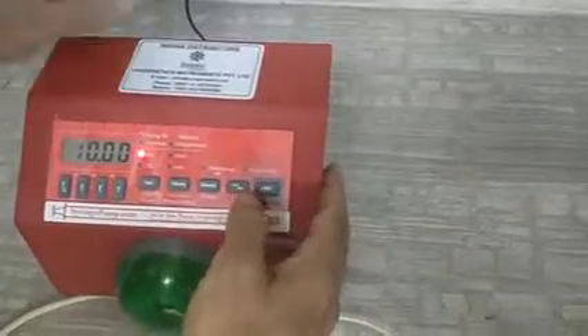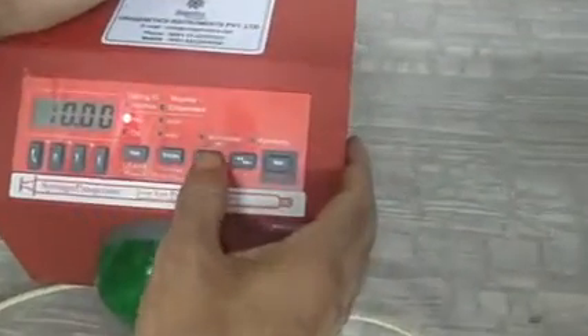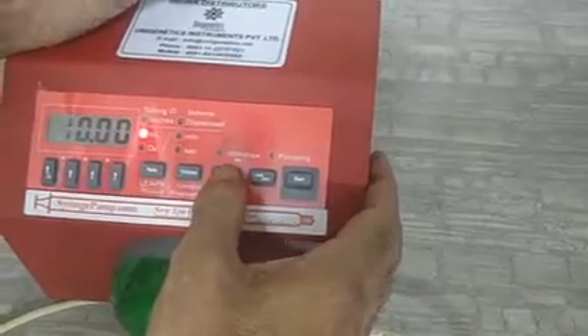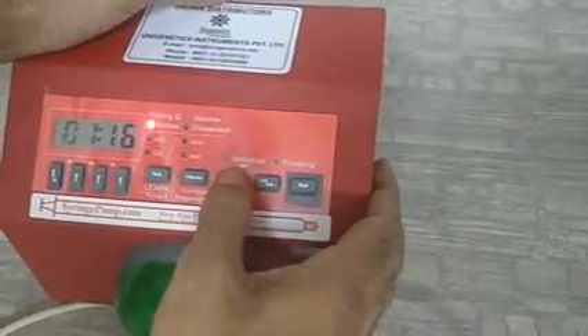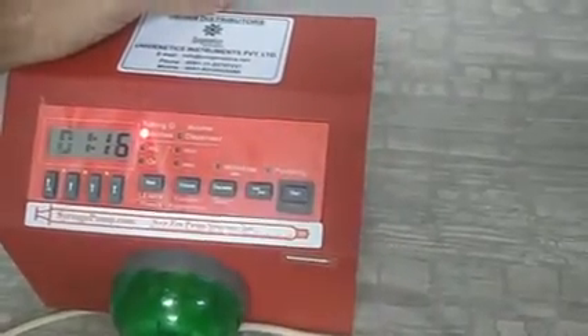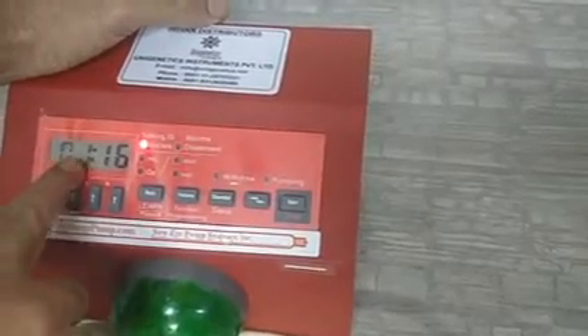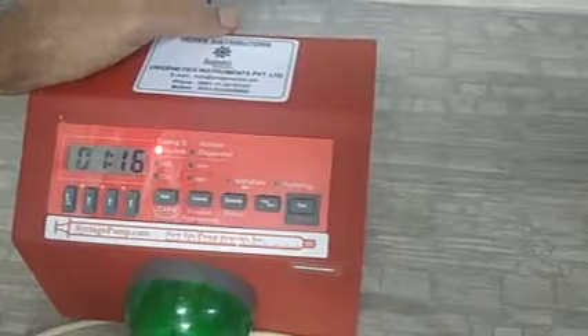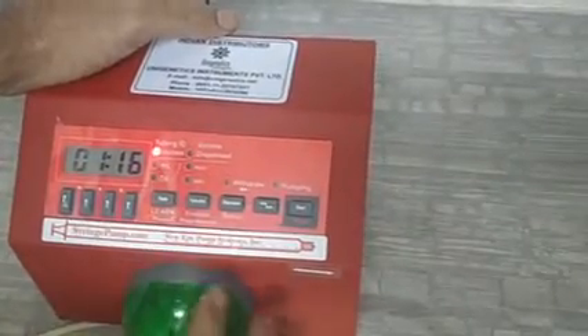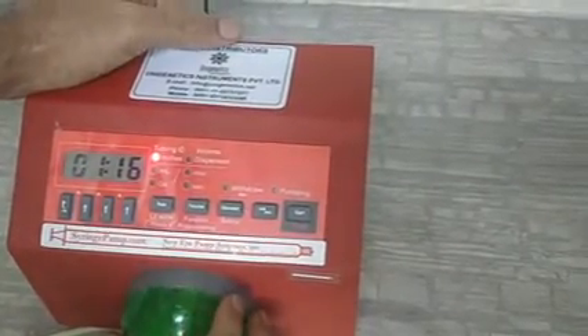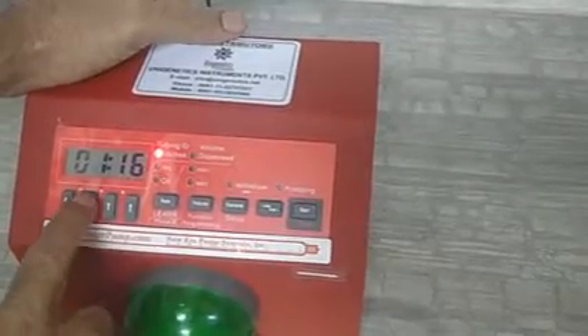Once the volume and the rate are set, one more thing is we have to set the diameter of the tubing also. For setting the diameter, you press the diameter and you see that this is 1 by 16 inches, and if you are using some other tubing you can change it. Suppose I use a different head with 3 by 16 inches, so I will make it that.